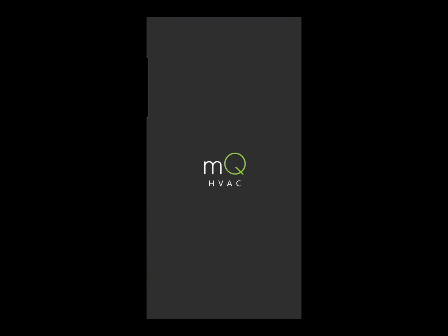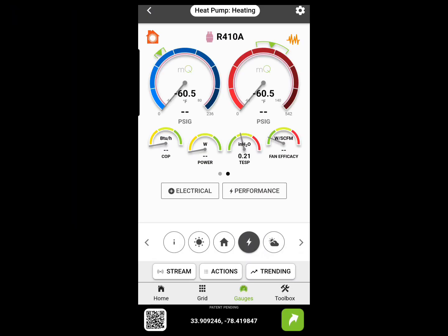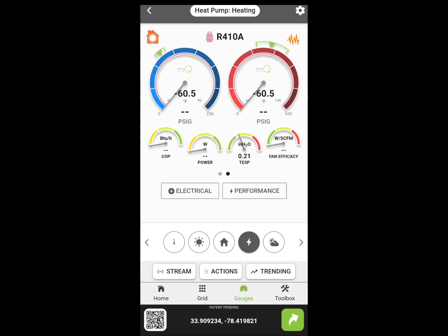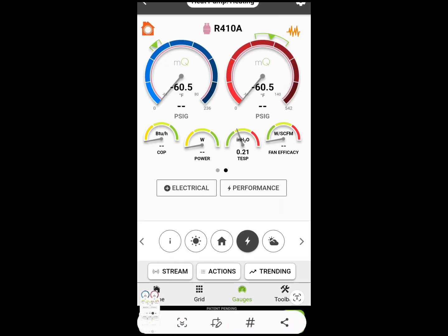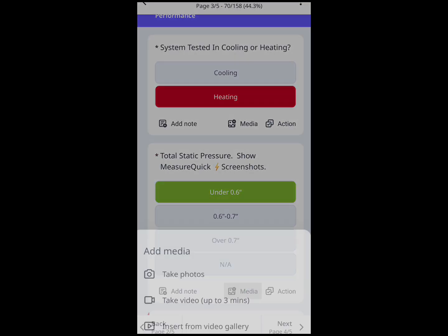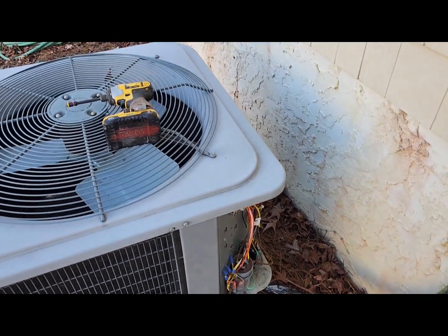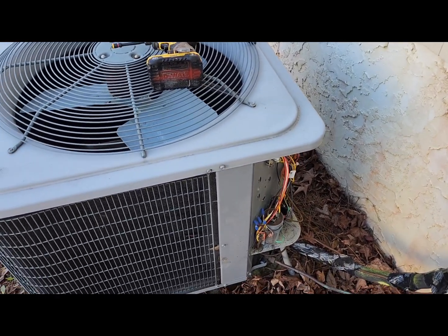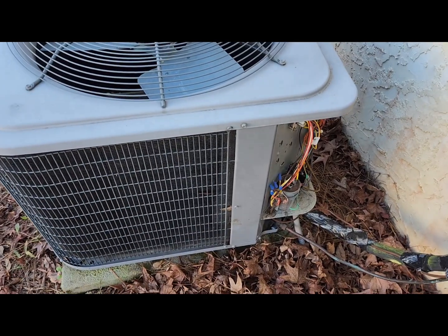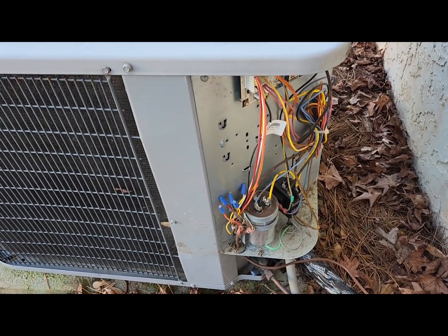We need to get this unit up and running to test it in heating mode. We open up MeasureQuick and do some basic setup — we tell it how many tons the unit is, whether it has a TXV, and the approximate SEER rating, so the app knows where those needles are supposed to go. But this unit is not running and we're going to have to figure that out. The contactor's not pulled in, so we now have to diagnose why it's not running.